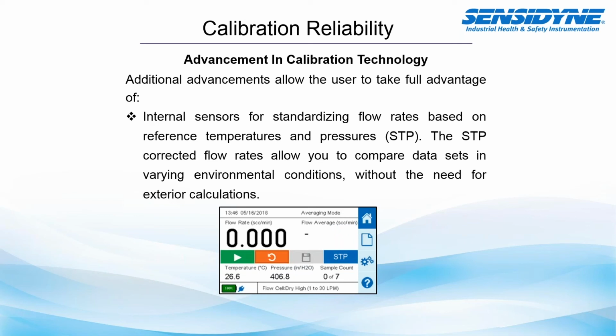Additionally, internal sensors for standardizing flow rates based on reference temperature and pressures can be put in place. As I mentioned earlier in the presentation, newer calibrators will actually be able to show ambient temperature and ambient pressure. And because these are important factors, you want to make sure that your starting or pre-calibration conditions can be compared to your post-calibration conditions. The STP-corrected flow rates allow you to compare data sets in varying environmental conditions without the need for exterior calculations. So in the past, industrial hygienists have had to do this manually to make sure that you held a steady rate between your pre and post calibration sampling events. However, now with calibrators that can actually do this conversion or standardizing, you can actually have the instrument do it itself without having to do this calculation manually.